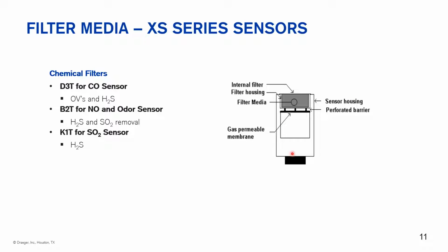Just a quick look, this is our older XS series sensor. This was a sensor, or is a sensor, we use in our older X-am 7000. And we do have, for some different sensors, different filter cartridges that can go in the top of the sensor. If that filter cartridge gets saturated, you can remove the filter and replace it without having to replace the whole sensor.